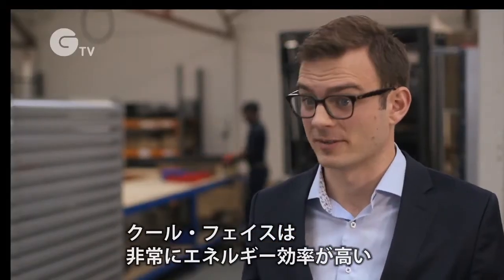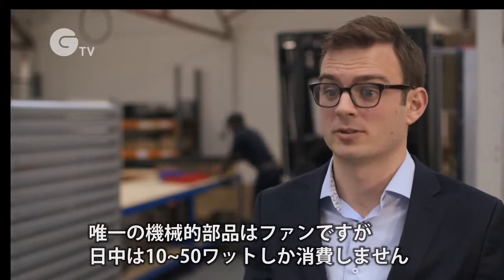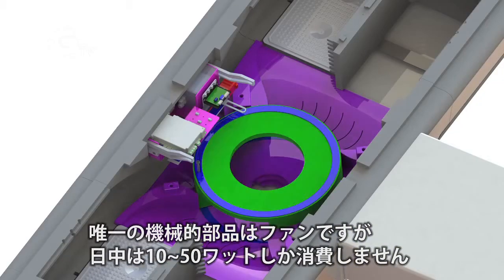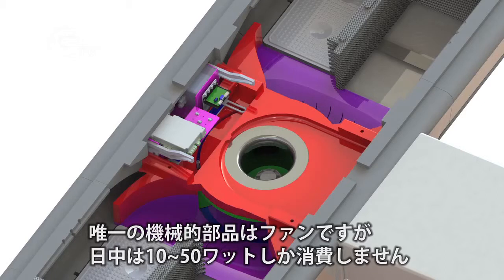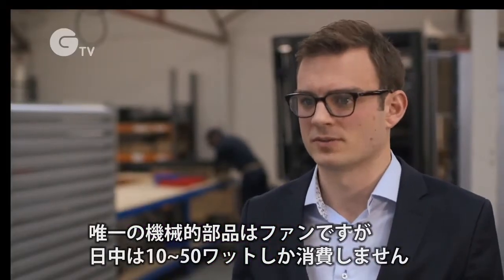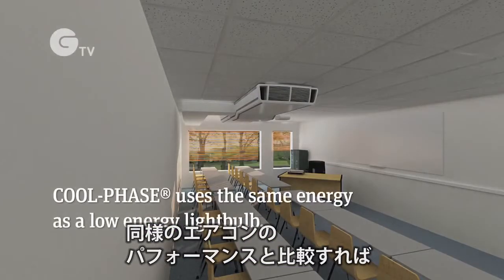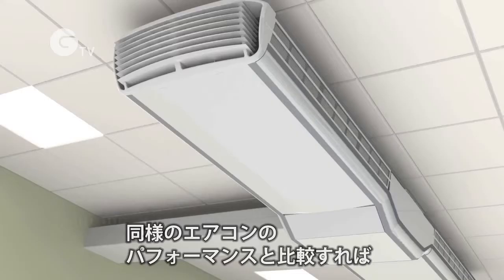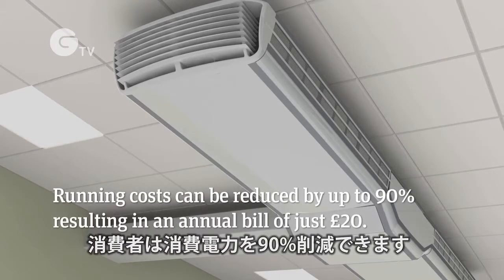CoolPhase is an incredibly energy efficient technology. The only mechanical component of the system is the fan that's housed in the air handling unit, and that will use typically from 10 to 50 watts during daytime running mode. So when we compare that to the performance of an equivalent air conditioning system, an end user can typically look at saving in the region of 90% compared to that conventional cooling approach.